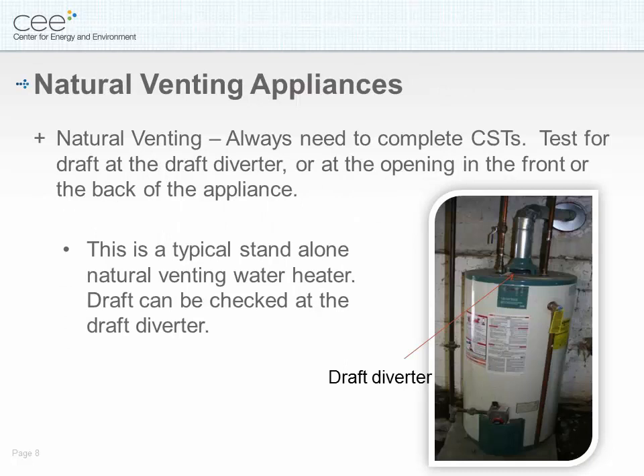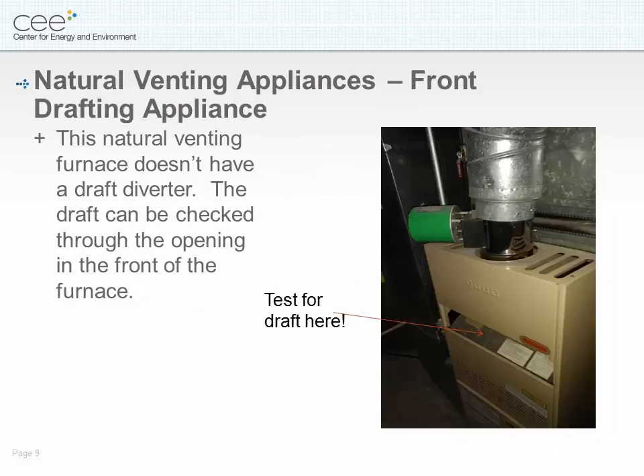Natural venting appliances. You always need to complete a combustion safety test. Test for draft at the draft diverter or at the opening in front or the back of the appliance. This is a typical standalone natural venting water heater — draft can be checked at the draft diverter. This natural venting furnace doesn't have a draft diverter; the draft can be checked through the opening in the front of the furnace.